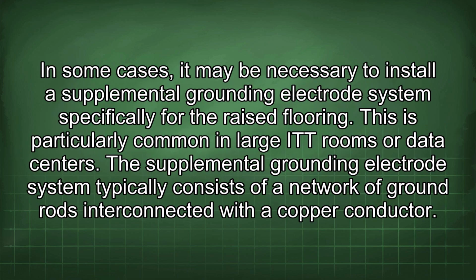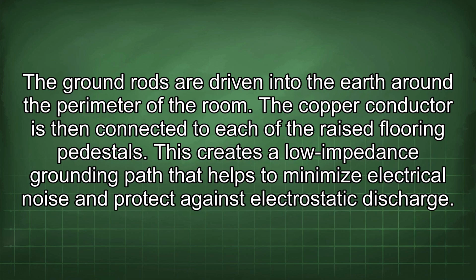In some cases, it may be necessary to install a supplemental grounding electrode system specifically for the raised flooring. This is particularly common in large IT rooms or data centers. The supplemental grounding electrode system typically consists of a network of ground rods interconnected with a copper conductor. The ground rods are driven into the earth around the perimeter of the room. The copper conductor is then connected to each of the raised flooring pedestals. This creates a low-impedance grounding path that helps to minimize electrical noise and protect against electrostatic discharge.